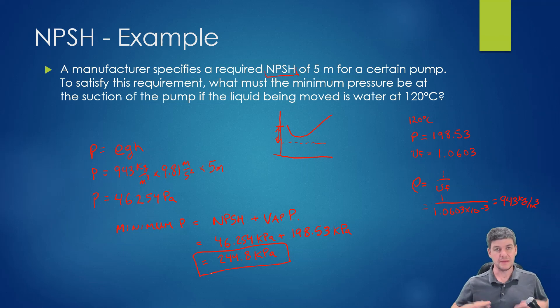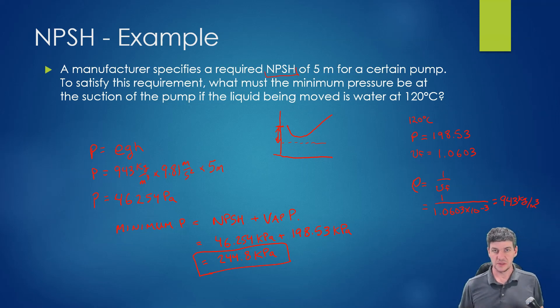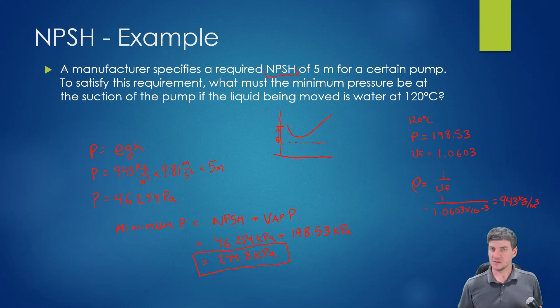When finding the minimum pressure required at a pump inlet, we use the pressure equivalent of NPSH and add the vapor pressure, because vapor pressure changes with fluid temperature. If the fluid is too hot, even a high NPSH value may not prevent cavitation.